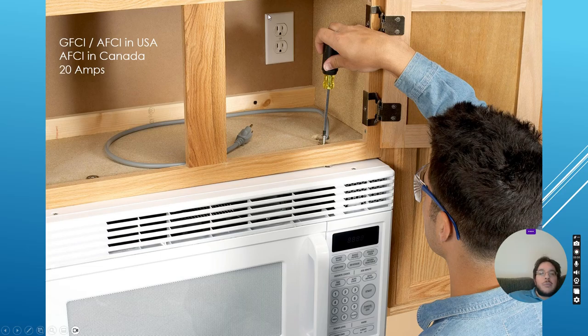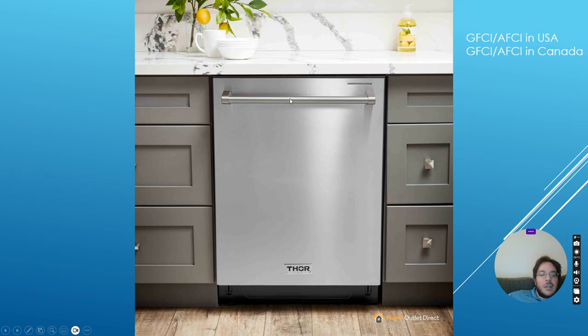Now, the funny thing is, microwave is the only place where you can have a receptacle in a cupboard. So generally you can't have a receptacle in a cupboard because of a fire hazard if you forget about it, but the microwave is allowed because it's intended for the microwave. And then technically, there's no rule that says you have to have a receptacle and a separate circuit for a dishwasher, but you generally do because there's a rule that anything over 1500 watts needs a receptacle, so that's 12 amps, and most dishwashers draw more than 12 amps, so you definitely need a receptacle for your dishwasher. It's got to be GFCI and AFCI rated.